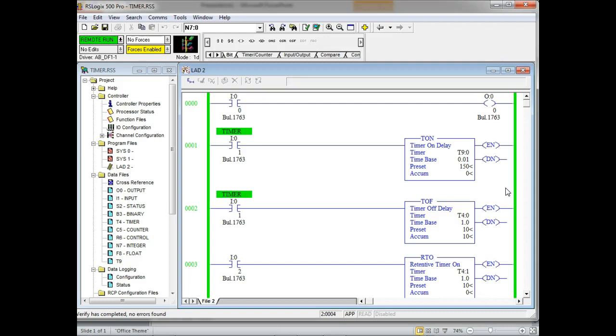And how do we reset that one? We make the rung true. So as soon as I make the rung true, right? So to reset the on delay, we make the rung go false. Y'all understand that, right? Okay? To reset an off delay, we make the rung go true, right? Okay. On an on delay, the done bit sets when the rung is through timing. On an off delay, the done bit resets or goes false when it's through timing.